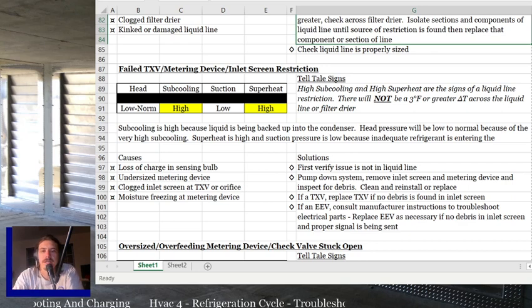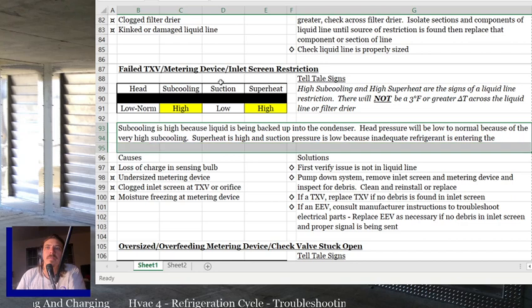So it means it's not in the line set. The issue is in the metering device itself or at the inlet screen of it. So the subcooling is high because the liquid's being backed up in the condenser. Head pressure is low to normal because of high subcooling. Superheat is high, suction pressure is low because the inadequate refrigerant is entering the evaporator.